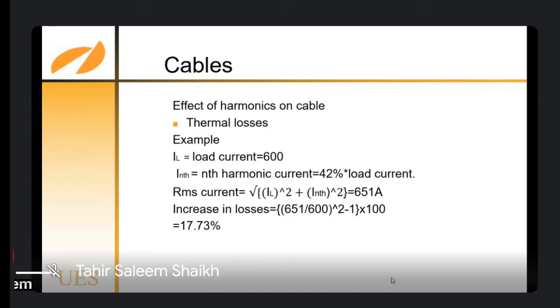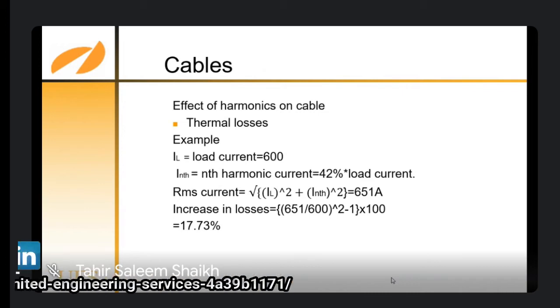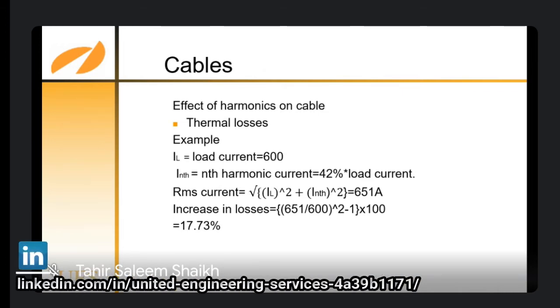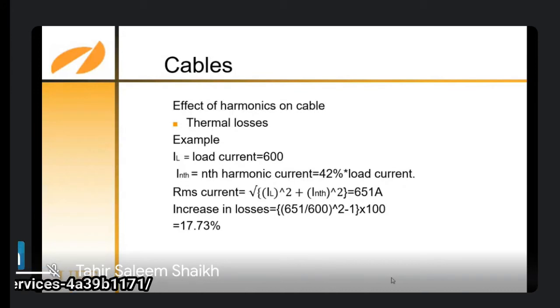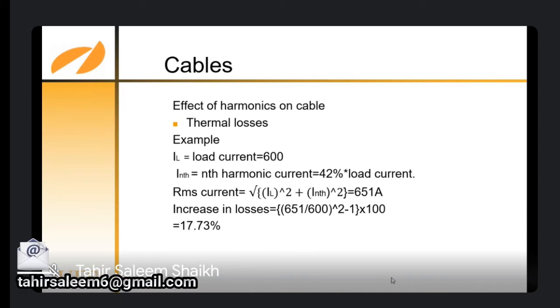Now you can see this example. The losses increase up to 17.73%. This is a simple example of how the thermal losses increase in a cable, and you have loss of energy also if the heating increases. In this example, the load current is 100% and the harmonic level current is 42%. Therefore, applying this formula gives you a 17.73% increase in losses.